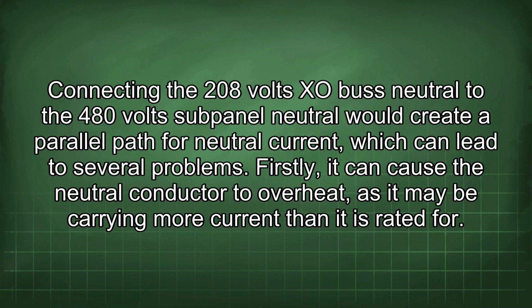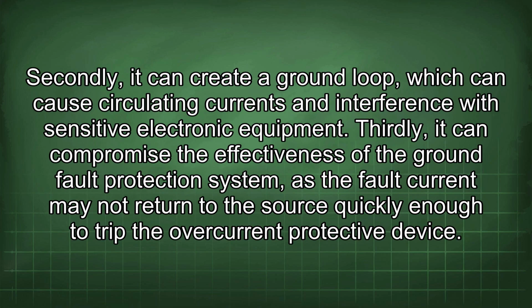Firstly, it can cause the neutral conductor to overheat, as it may be carrying more current than it is rated for. Secondly, it can create a ground loop, which can cause circulating currents and interference with sensitive electronic equipment. Thirdly, it can compromise the effectiveness of the ground fault protection system, as the fault current may not return to the source quickly enough to trip the overcurrent protective device.